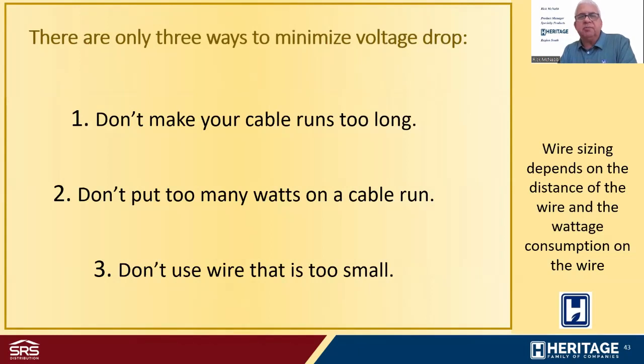So the way we manage voltage drop, there's really only 3 things we can do. In other words, don't make your wire runs too long. There's a limit to how far you can go with the wire. Don't put too many watts on a cable run. Or you could even say don't put too many fixtures on a cable run. There's a limit to how many fixtures you can have, which is a corresponding wattage maximum you can have on a wire run. And number 3, don't use wire that's too small. You always want to be sure you use the right size wire for your length of run and your wattage consumption on that wire. Wire sizing depends on the distance of the wire and the wattage consumption on the wire.